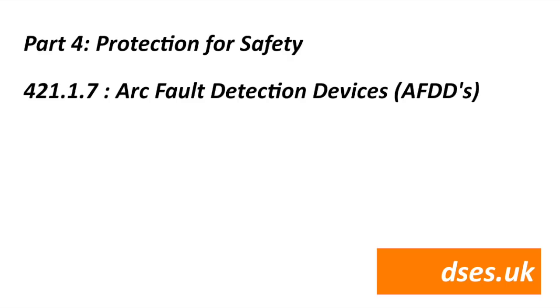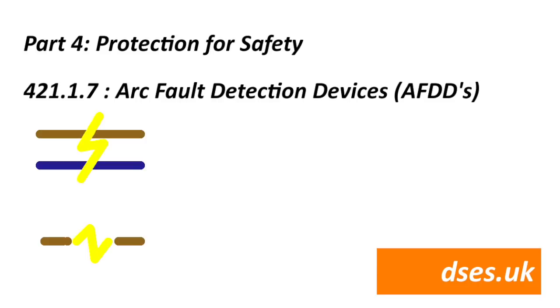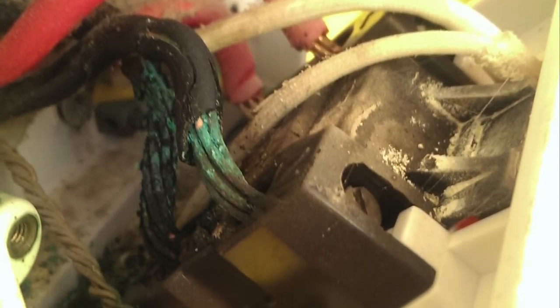On to protection against thermal effects and Regulation 421.1.7 — the use of arc fault detection devices, or AFDDs, also known as arc fault circuit interrupters or AFCIs to our American cousins, where they've been in use for some time. An AFDD is a clever bit of electronics that can detect an arc between conductors or on a series line and cut the power before thermal damage causes a fire. The electronics detect different arc signatures, so a natural arc when a mechanical switch is thrown won't trip the device, but an arc across a loose connection or between cores on a damaged cable will actuate it — the kind of fault that causes burnt-out shower isolators.